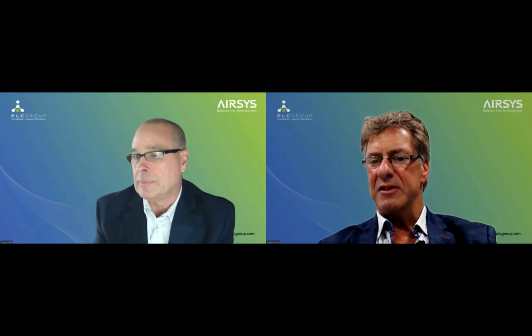Here's a question from Mark Hanjani. Rack density for AI data centers is over 100 kilowatts. How would a server-level liquid solution integrate? What is your experience on, say, a 5 megawatt data center and the building footprint required to accommodate it? Well, that's a great question, but because we really haven't deployed the liquid rack at scale, that is a site discussion going on currently. Like I mentioned earlier, you've got a chiller to a CDU to a rear door heat exchanger. What is the evolution of that going from a 100 kW rack to, let's say, 220? That is something we really haven't solved yet, without saying that you're probably going to have to replace that rack with a liquid rack if you're going to those higher densities.